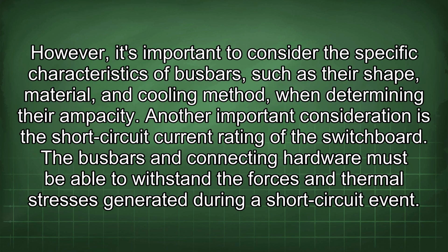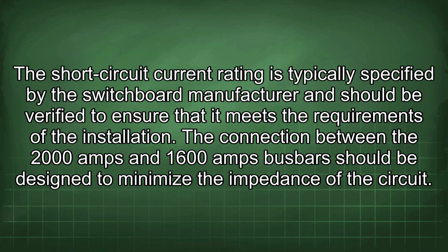However, it's important to consider the specific characteristics of busbars, such as their shape, material, and cooling method, when determining their ampacity. Another important consideration is the short-circuit current rating of the switchboard. The busbars and connecting hardware must be able to withstand the forces and thermal stresses generated during a short-circuit event. The short-circuit current rating is typically specified by the switchboard manufacturer and should be verified to ensure that it meets the requirements of the installation.